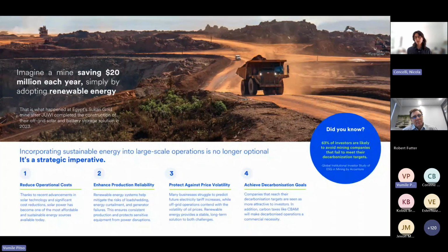Because we're exposed to the execution side, it's a challenge because you're subject to the same grid queuing rules as straight embedded generators, even though you're not a normal generator. So it's a challenge to get onto the grid. But to engineer, design and install bidirectional meters and allow for that in your control system isn't really an issue - it's more about just getting past the utility and then being hit with the bill for upstream costs.